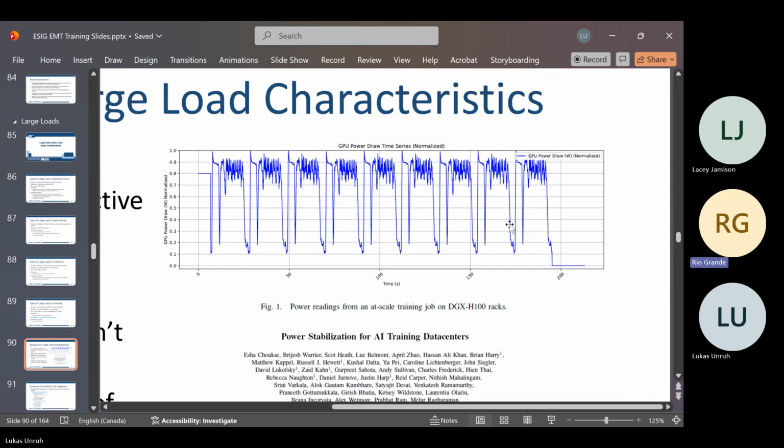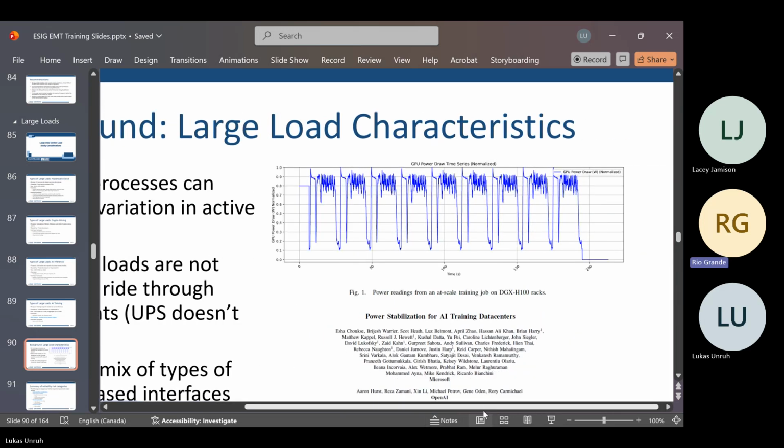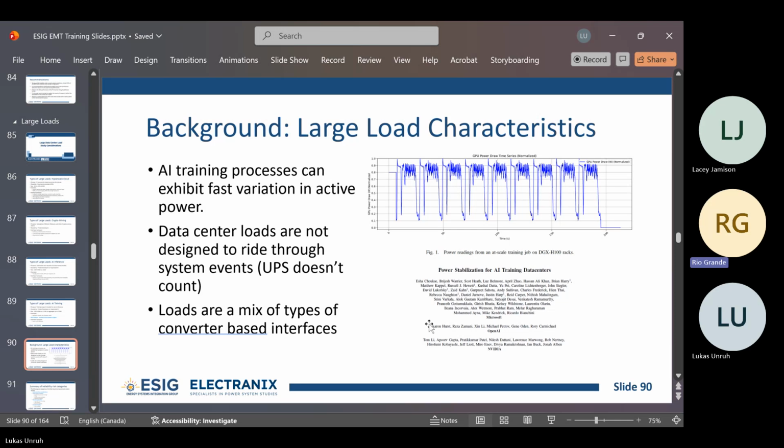And this process, what we're hearing, is basically synchronized across the entire facility in large part. So these dips won't occur at time X on GPU 1 and time Y on GPU 2. Generally, they're synchronized across the facility. This is I guess the most efficient way to do the training, which is the main priority for these facilities: to train the model as quickly as possible.